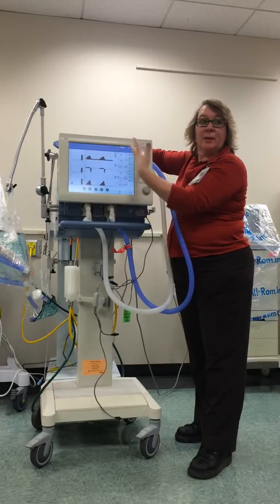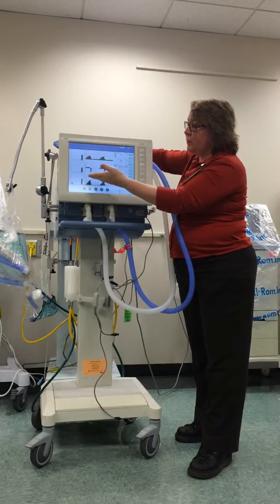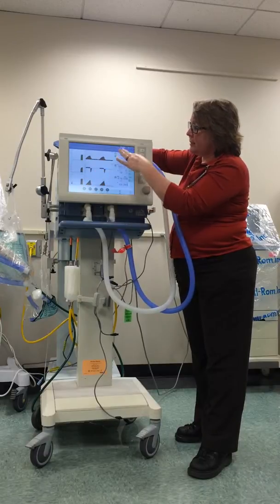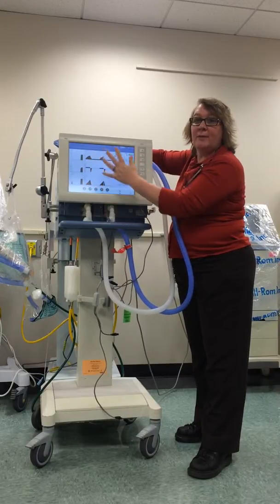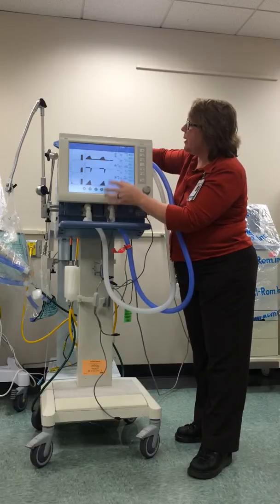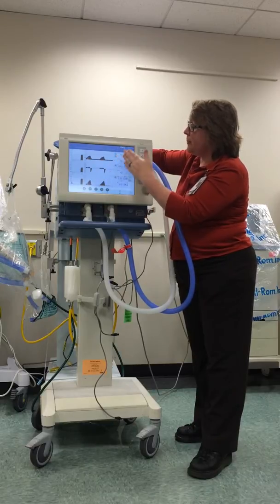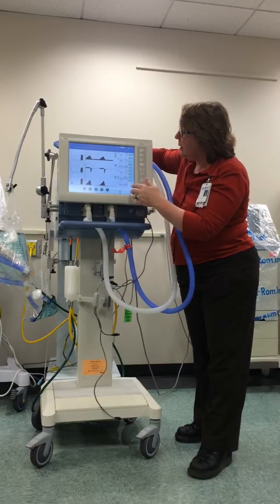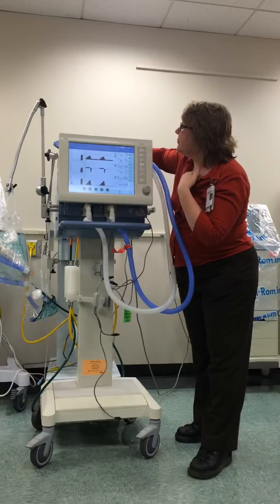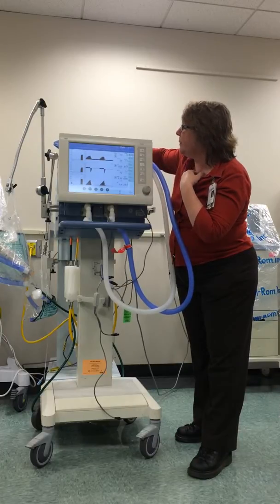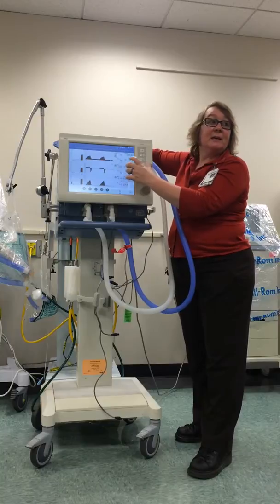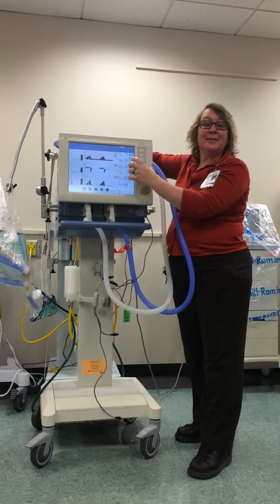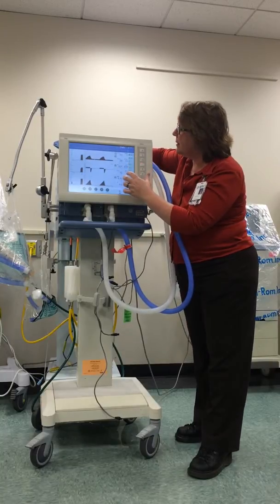Typically, most of the time, this is how we'll leave our screen. We'll have our 3 waveforms, our set settings, and our patient settings that we could look at to have all this information all the time. I want to see my peak pressures, my peak. I want to have all of that there. Let's see. So we know peak is our PIP. This has got VT and VTE. Remember, we want to use the VTE for our vent checks.